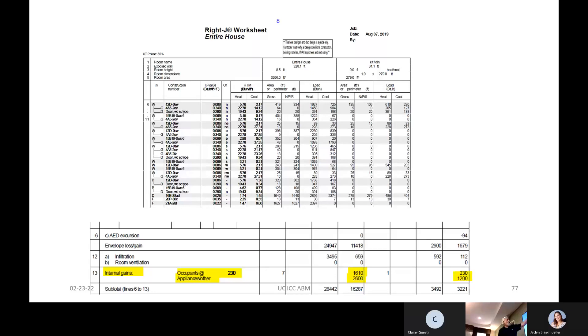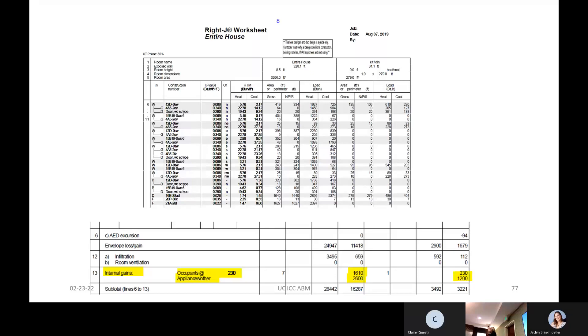Here's the orientation we talked about earlier. Pick a room and see if it matches what the plans are telling you — that we have 135 square feet of gross wall facing north, using their wall height numbers. Now, rim joists need to be accounted for somewhere — whether you put it in the room above or the room below. Rim joists should be accounted for because it's wall. I'm not going to send it back just because you have a one-foot wide strip, but it is part of it.